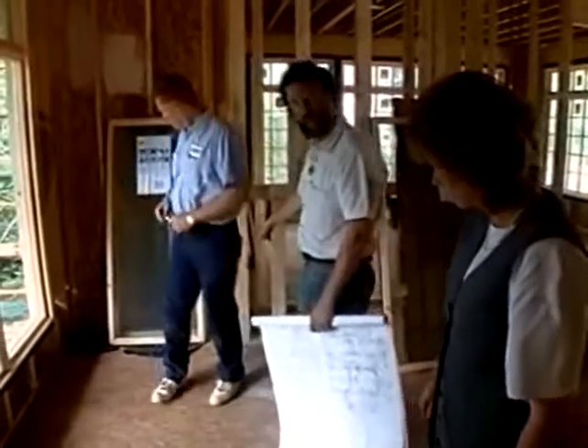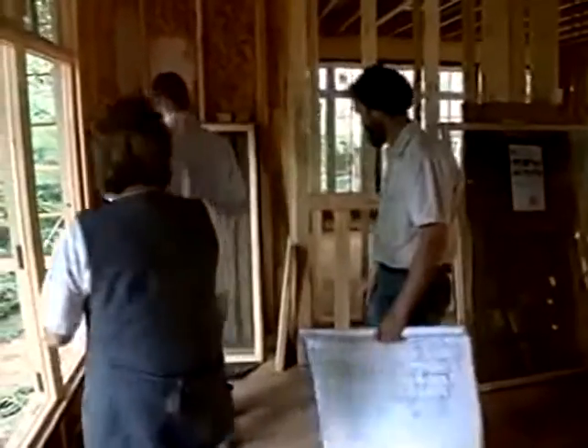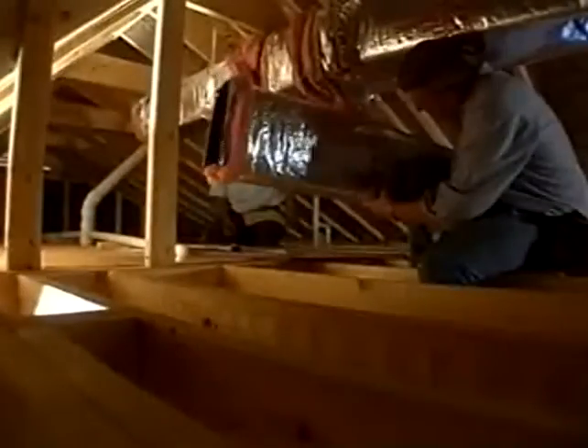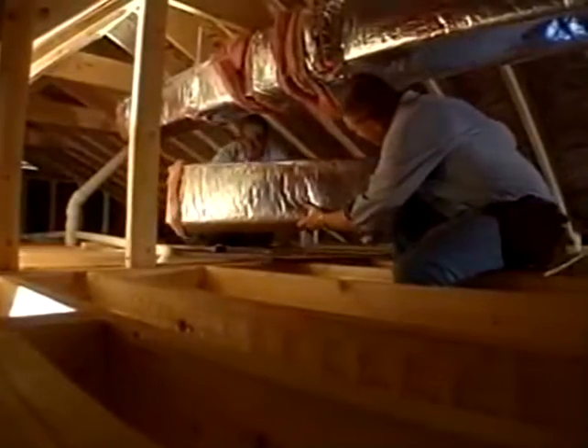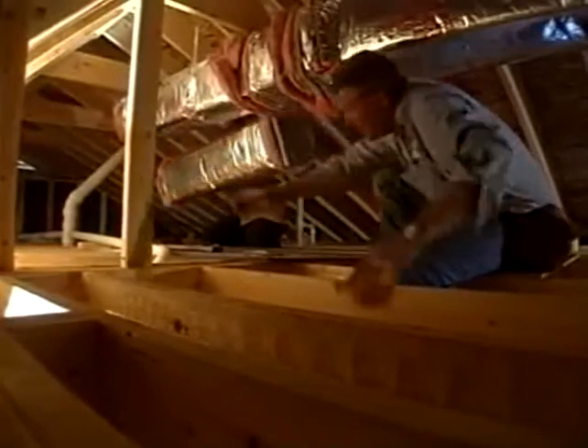The design of the air distribution system can affect more than comfort. It can also impact the health and safety of homeowners. I can't tell you how many people complain about everybody wanting to go to bed at night and close their doors, and then the room gets hot and stuffy, so they have to leave their door open all night. And not to mention the indoor air quality aspects of that, because if some rooms are going positive, obviously some rooms are going negative. And when that happens, they can carry contaminants with them. You can get backdrafting of equipment and things like that, and it becomes a real health risk.